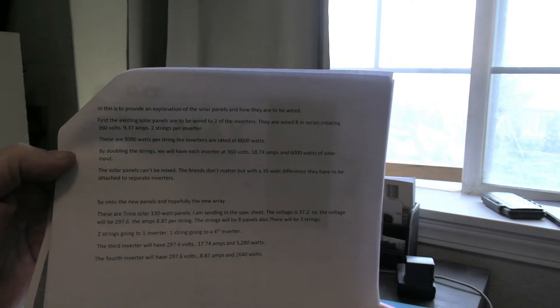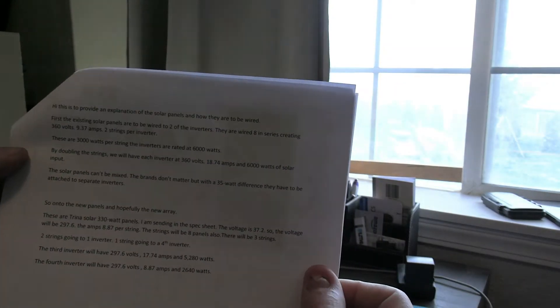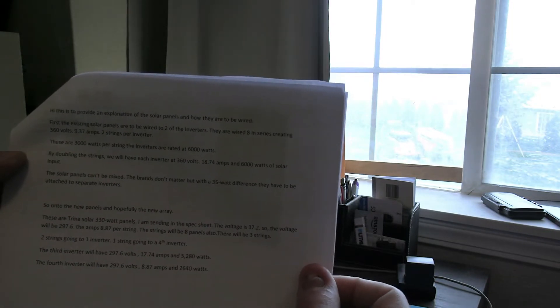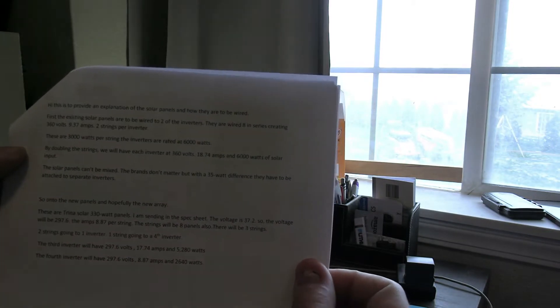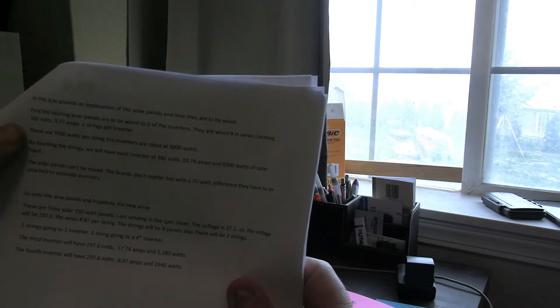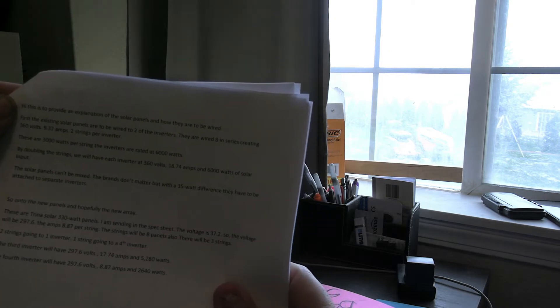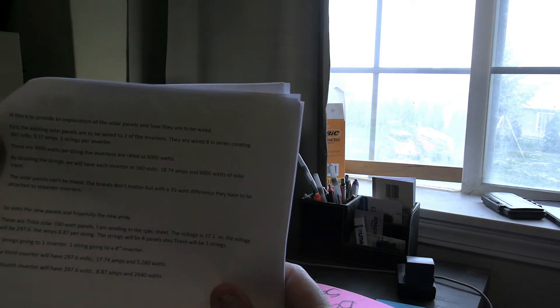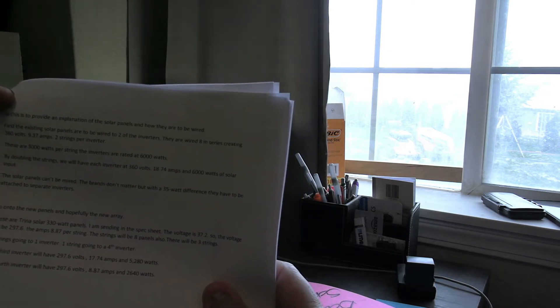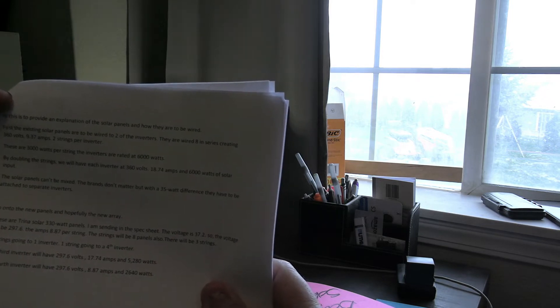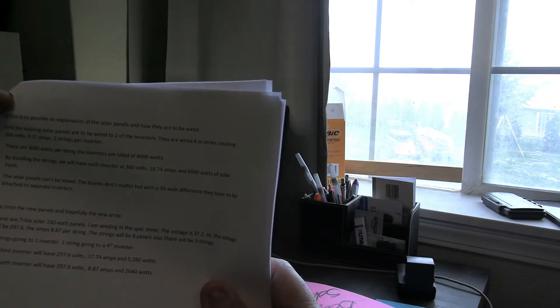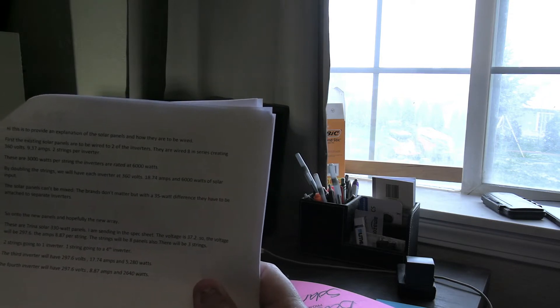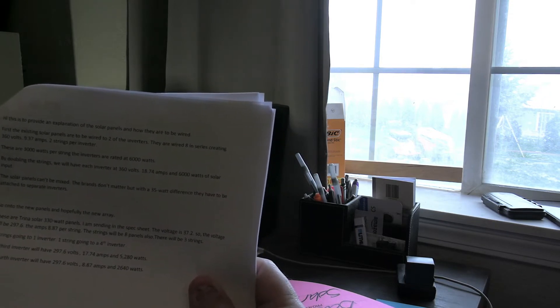So this is to provide an explanation of the solar panels and how they are to be wired. First, existing solar panels are to be wired to two of the inverters. They are wired eight in series creating 360 volts, 9.37 amps, two strings per inverter.